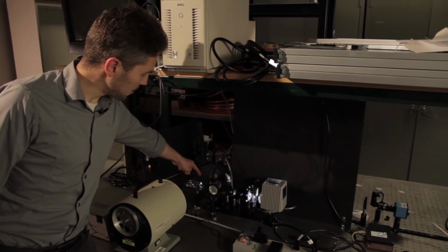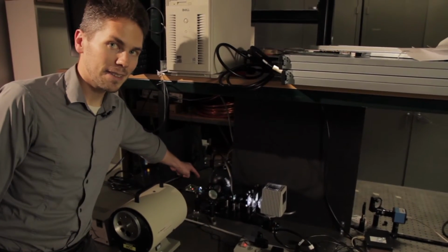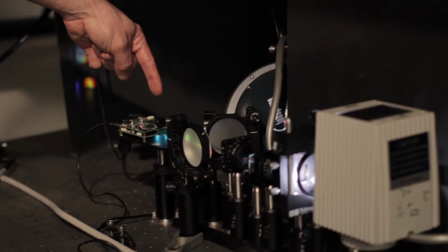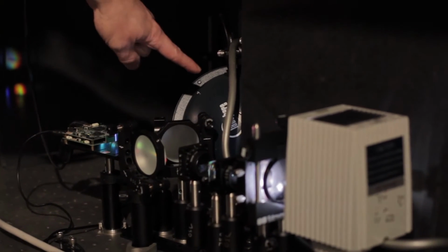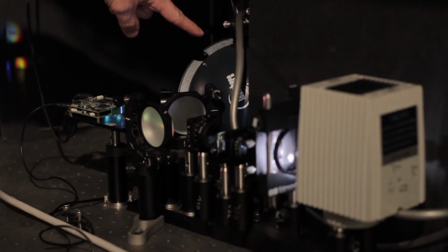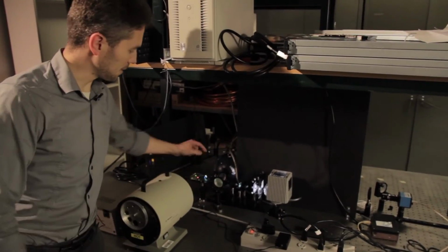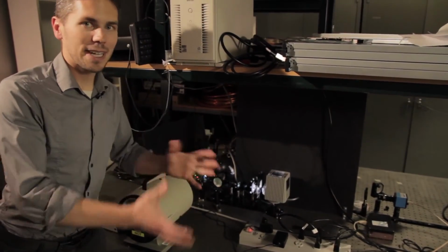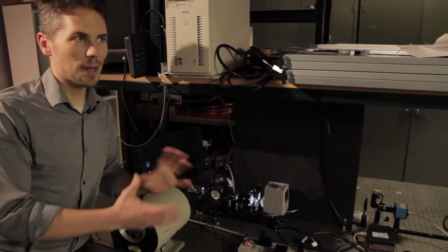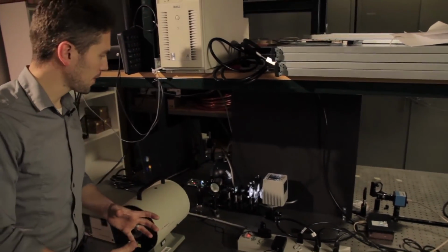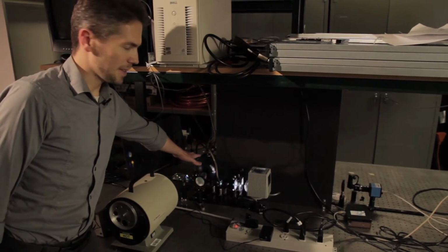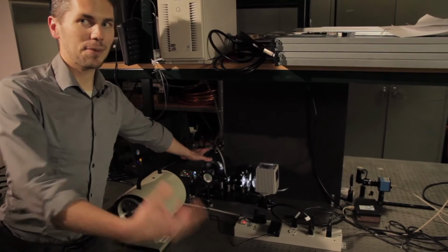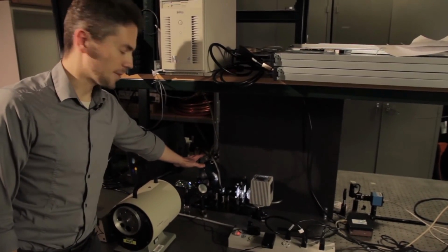What we're able to do is selectively reflect light from this location into what's called an integrating sphere. This sphere essentially takes that light that we're selecting here and homogenizes it, smooths it out spatially, makes it more spatially uniform. This is the light that we're most interested in observing with our instruments or our sensors. So we can use this light to calibrate our instruments, which enables us to make our observations in the field.